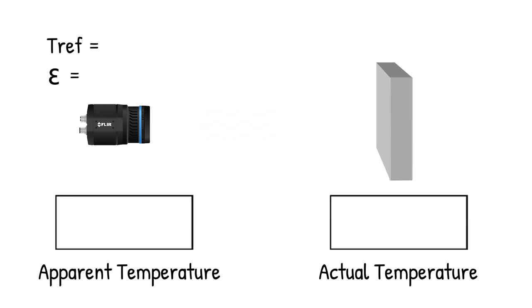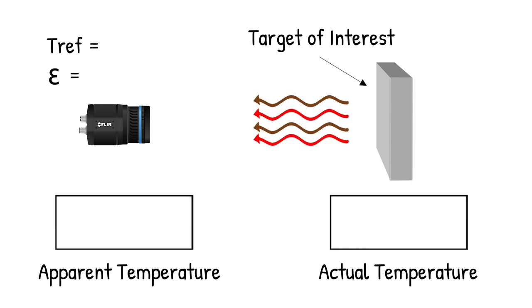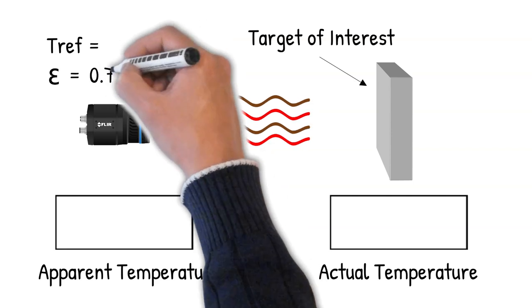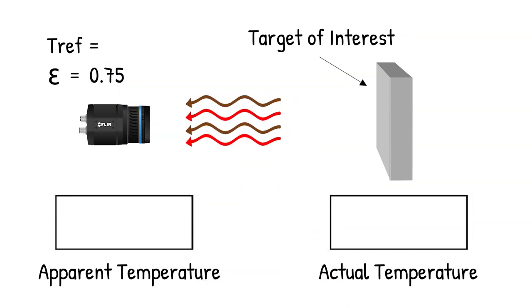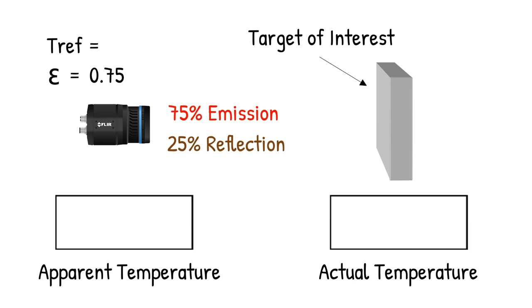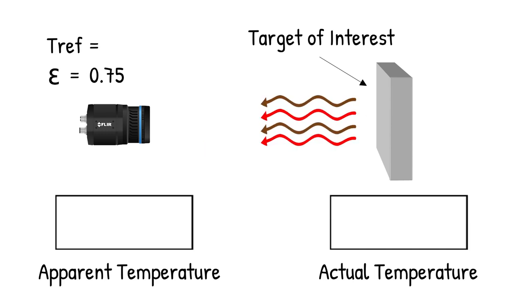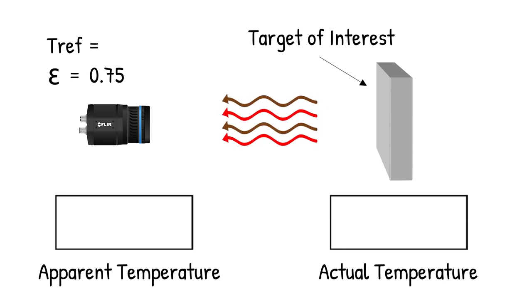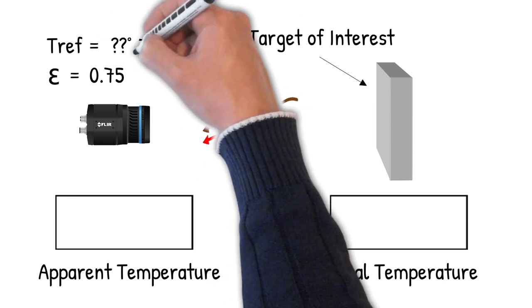In this example, the target of interest is opaque, meaning there is no radiation transmission through the target, and the target has an emissivity value of .75, or in other words, the total radiation from the target will be 75% emission and 25% reflection. If no emissivity adjustment is made to the infrared camera, how will the reflected radiation impact the camera measurement?